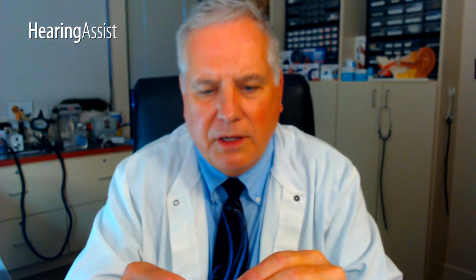I want to explain to you the buttons on this device. It has a multifunction button right on top, right here. If the hearing aids are off and you hold it down for 3 seconds, they're going to turn on. The light's going to flash 3 times and then go out, and about 10 seconds later the sound will come on and you'll hear 1, 2, 3, or 4 beeps based on what program you left the hearing aids in. If I press that button for 7 seconds while they're on, it's going to turn the hearing aids off. But you don't really have to worry about that too much.